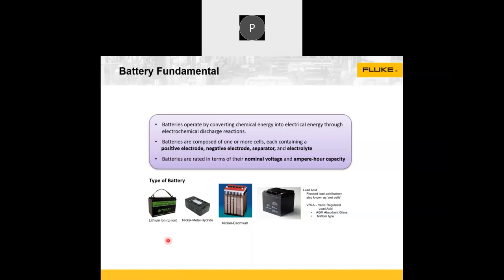Interestingly, specific gravity testers are good for open type batteries, where you have access to collect the solution and test the chemical composition or pH levels left. But what happens if the battery is sealed? I think today you may be using more sealed batteries. In such conditions, you may need digital battery analyzers which help find the underlying electrolyte or heat conditions of the batteries in your facility. Even though these are called sealed maintenance-free batteries, there's nothing like a truly maintenance-free battery in the world. If you don't maintain it, it will fail, and you'll end up facing failures and downtime in your systems.